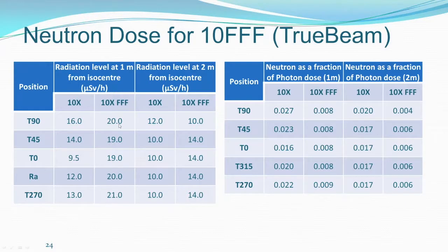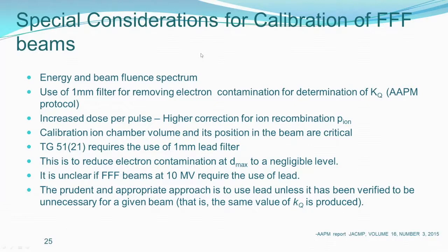So when I normalize this to the photon, then 10X FFF actually gives you much lower neutron contribution compared to 10X. So it has to be normalized to the amount of photon that it generates. There are special considerations you have to look at when you calibrate a FFF beam. Actually, I took it from the AAPM report.